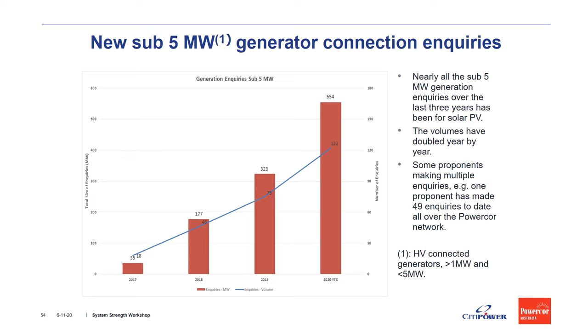We have seen some proponents making multiple inquiries. For example, one proponent has made 49 inquiries to date all over the Powercor network. We believe this is an emerging system strength related issue, because if you look at the volume number here, it is equivalent to several large-scale inverter-based generators. So the impact of those new generators needs to be properly assessed and managed in order to ensure system security.